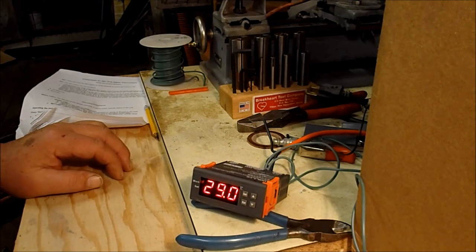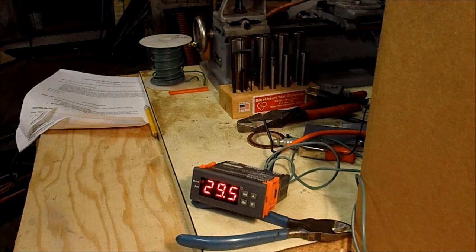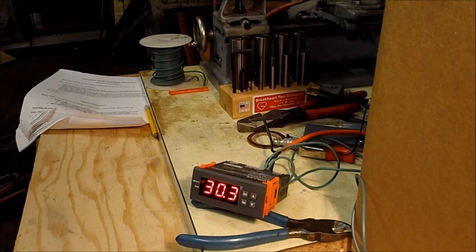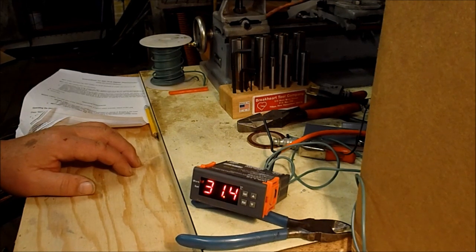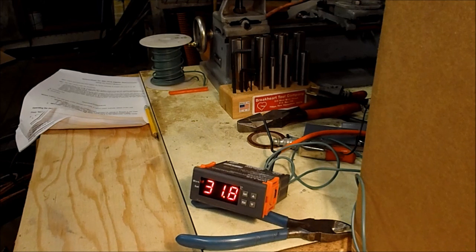We got new thermometers and we put all the thermometers in our incubators. I've got four or five of them in there. I got 10 thermometers. One was dropped right away and was ruined and rejected. The others are in the incubator and they all show exactly the same temperature. We put them in the different incubators with the digital thermometers, and the digital thermometers are way off. The bulb thermometers are showing a steady 100 degrees, just a little less than 100 degrees Fahrenheit. Our digital thermometers will show 94 degrees, 93 degrees, 99 degrees, 101 degrees. They just jump all over the place.